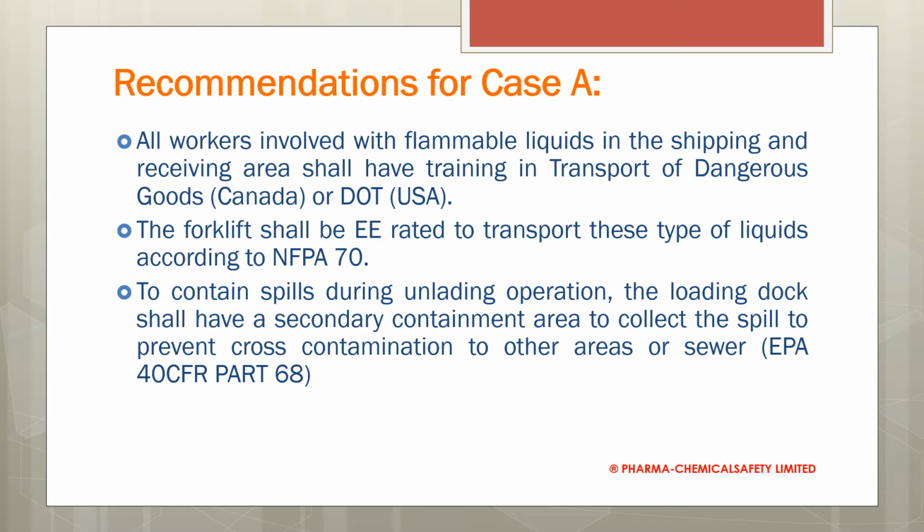Now somebody can say that is not necessary because we have a well ventilated area. That depends on what you mean. If you are complying with that, yes, you can argue that. But my recommendation, to avoid going to the next step, which is going into the red level room with a non-rated forklift, which is going to cause trouble, is to use the EE rated forklift to transport this type of liquids according to NFPA 70.